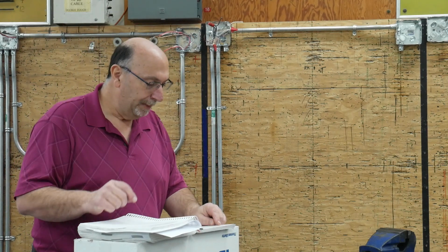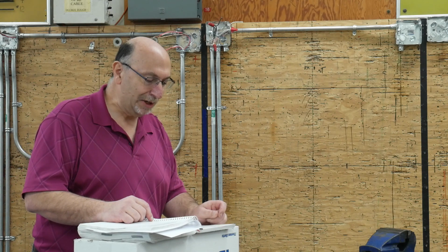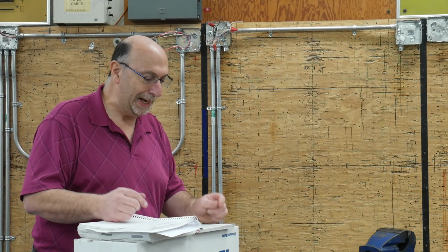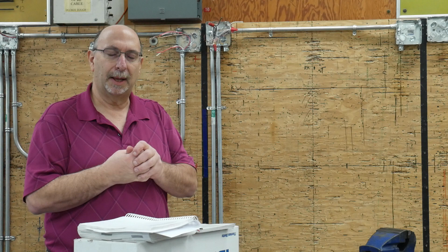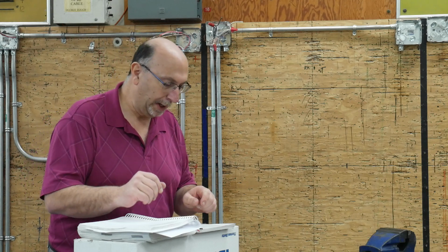So in sub-rule A, an insulated conductor running through a box with no connection therein shall be considered as one insulated conductor. So what we're trying to do with this rule is determine the minimum size of box that you require. So we have to do basically counting of the number of conductors in the box. We have to use other items, for example, the number of wire nuts that are in the box to determine the box size that's required.